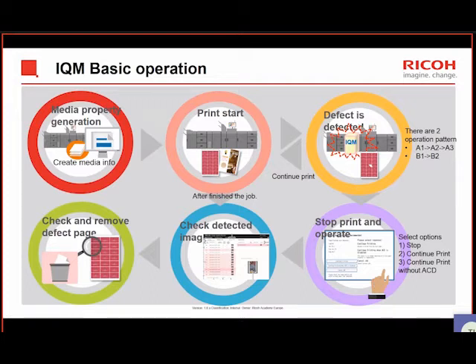It's the same error screen that we had on the 9200. It's on the operation panel, and it literally says you've got an error, and the error code is code 30, for example. It doesn't give you a message to say we've detected a white streak or a black streak. This message doesn't tell you that. You have to enter the user interface.